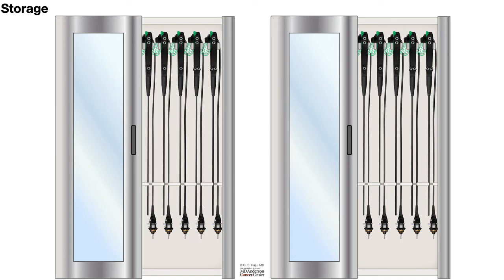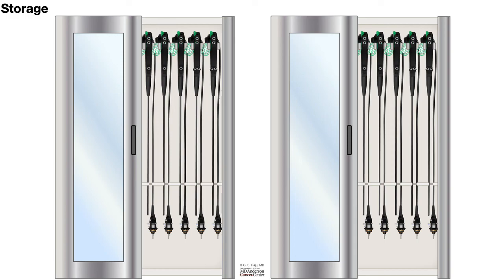We talked about manual drying, automatic drying, and then bringing the scope to the storage area and hanging it vertically down. There are some storage cabinets where continuous air flushing can be done. That also does the same purpose.